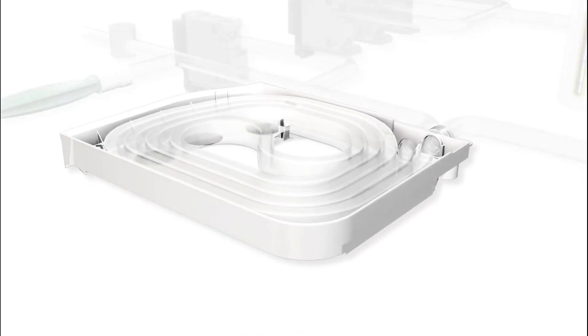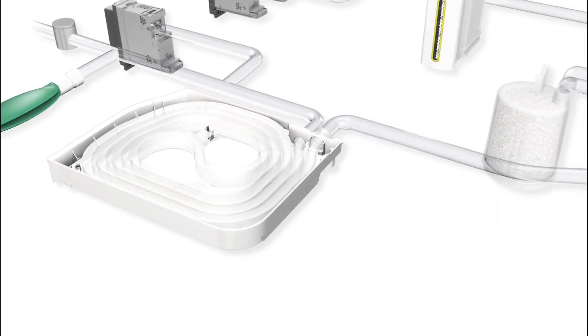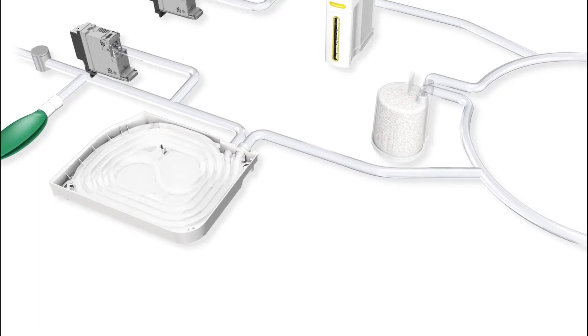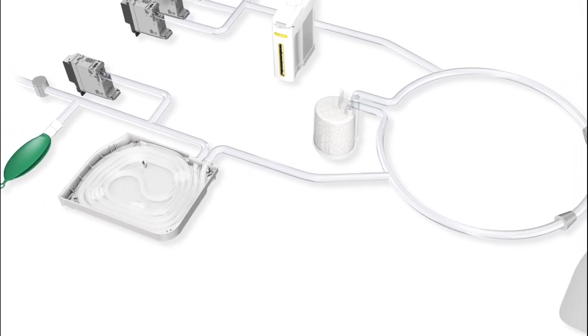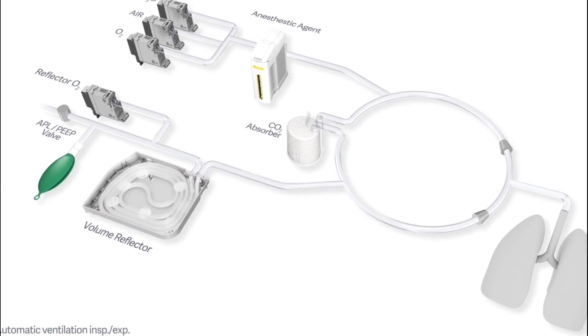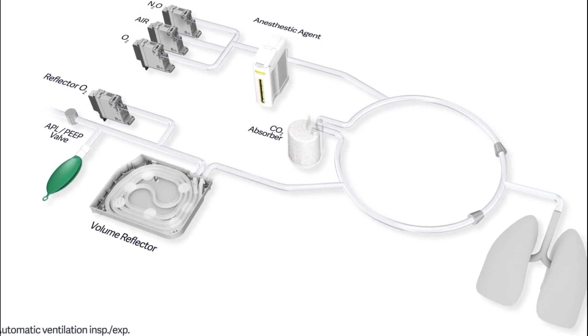Fresh gas flow leaves the anesthetic machine and passes to the patient via a one-way valve during inspiration. As expiration occurs, the exhaled gases from the patient pass via a one-way valve to the APL valve, then onto the reservoir bag or ventilator.